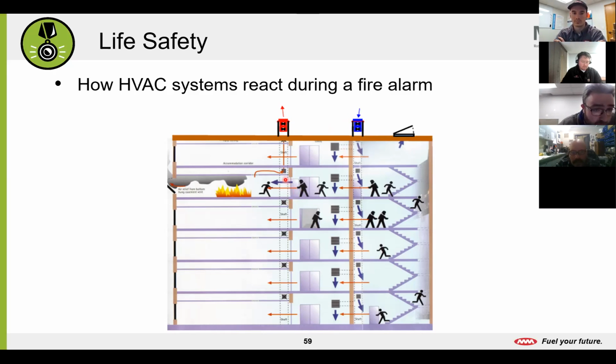And then if you look here on each one of these floors, we have these little boxes. These are what we call fire dampers. Their job is to stay open when everything's fine. And then when it senses either smoke or heat, its job is to respond accordingly, either close down or open up. So in this instance, we have a fire on the 5th floor. First thing that happens is our fire dampers on floors 1 through 4 all close down. The damper on floor 5 stays open, and we energize our corridor exhaust fan. What that's going to do is put this space right here where our incident is occurring into a negative. And what we're trying to do here is contain it.